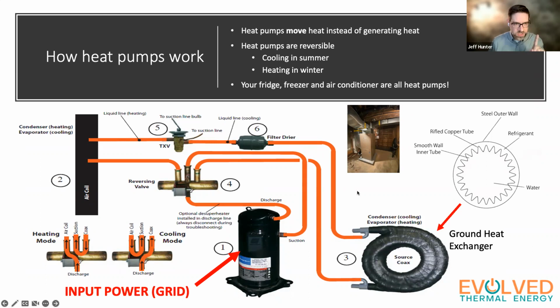Now, there's one thing missing from this graphic that we haven't discussed, and it's where this text is right here: it's called a desuperheater. Most of us know that ground source heat pumps can do heating and cooling, but they can also provide domestic hot water, and on our common systems, the desuperheater is what does that for us.